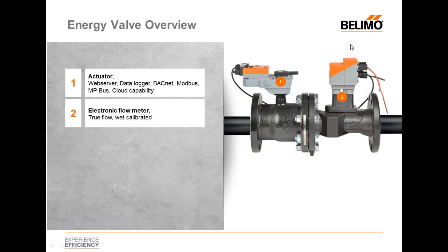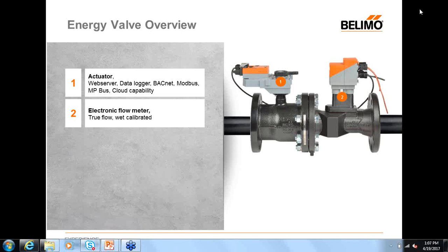Now I'll talk about the electronic flow meter. This is a picture of the new ultrasonic we are coming out with. It provides a true flow reading as opposed to a flow calculation like you would receive with a mechanical pressure-independent valve. You actually have a true GPM reading, and all of our ultrasonic flow meters will be wet calibrated, which means they're guaranteed for accuracy and repeatability as they're wet calibrated before they leave the factory.